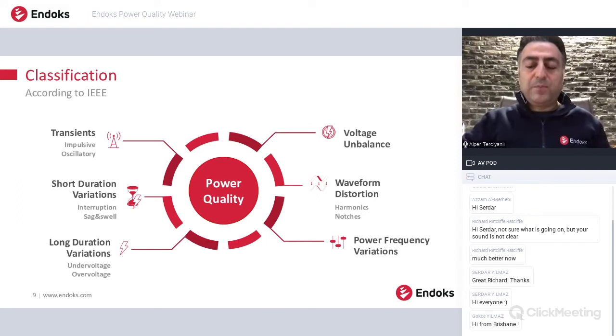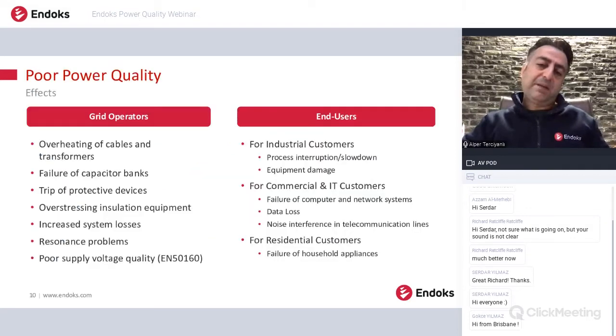I would like to mention one important thing here. Reactive power itself is not considered a power quality parameter in the standards. Voltage variation, which is a direct effect of reactive power flow, is a parameter. So personally, I prefer to classify reactive power flow as also one of the power quality parameters, in addition to those on this slide.